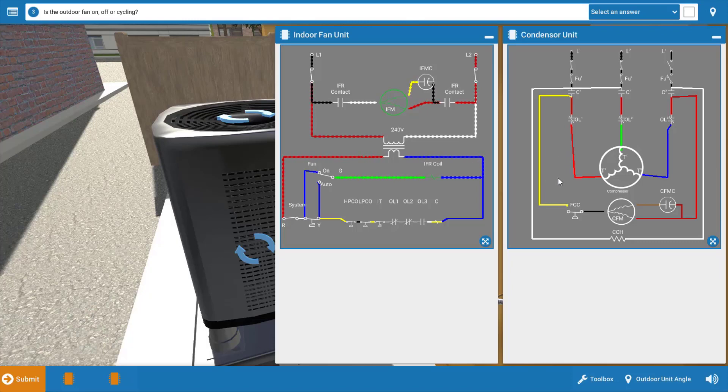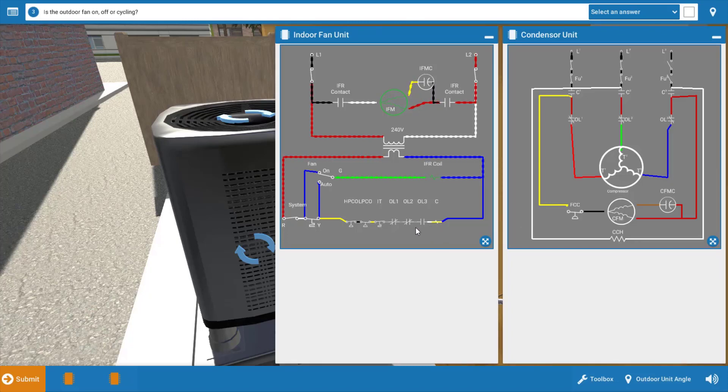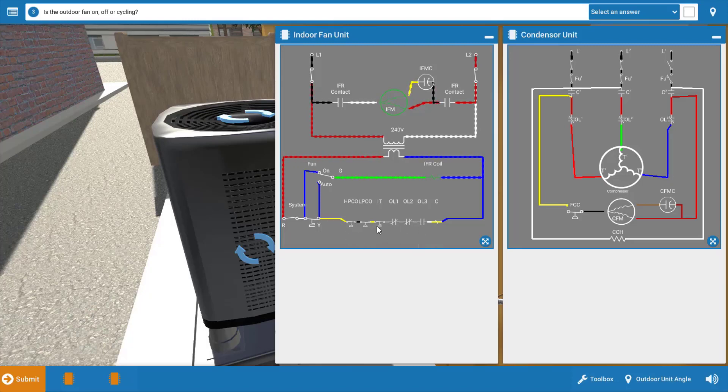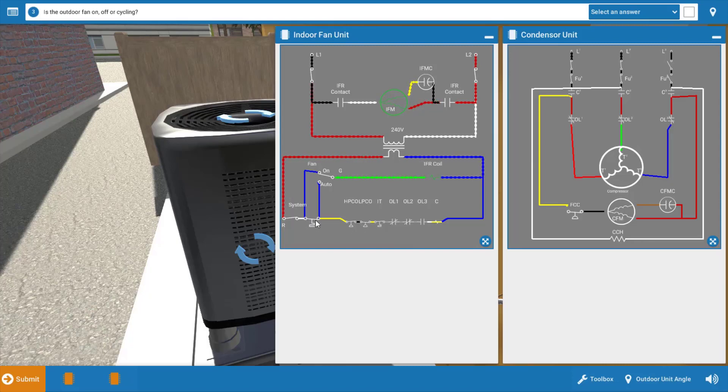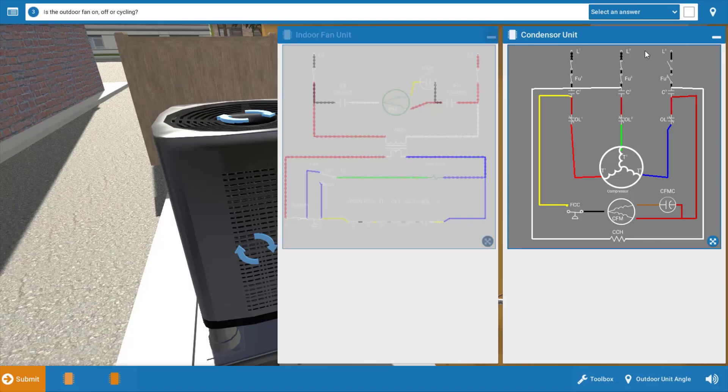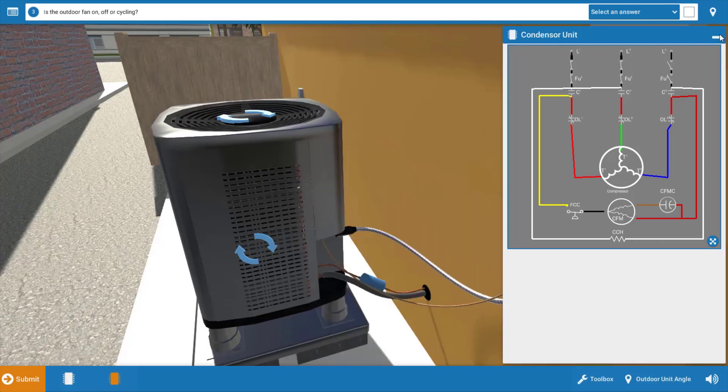So it's possible that this contactor coil is faulty, but it's also possible that any of these switches in series are faulty, meaning the three overload switches, the internal thermostat, one of the pressure switches, or possibly the thermostat contacts could be faulty. So we're going to narrow this down and we're going to eliminate each of these.